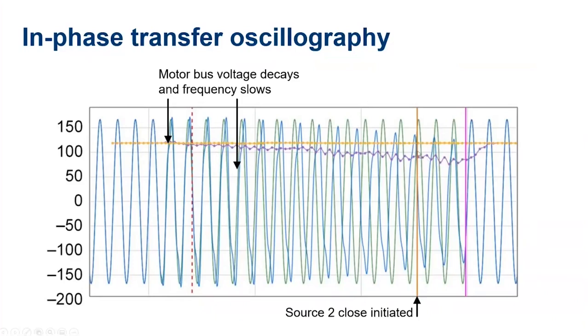And at this point, we determine that if we send the close command here, the breaker will actually close when the two signals are aligned again. And so that's what the relay does. And the system goes back to normal operation there. And we see that we only have a very moderate drop in the voltage. Okay, so that's where the in-phase close happens.